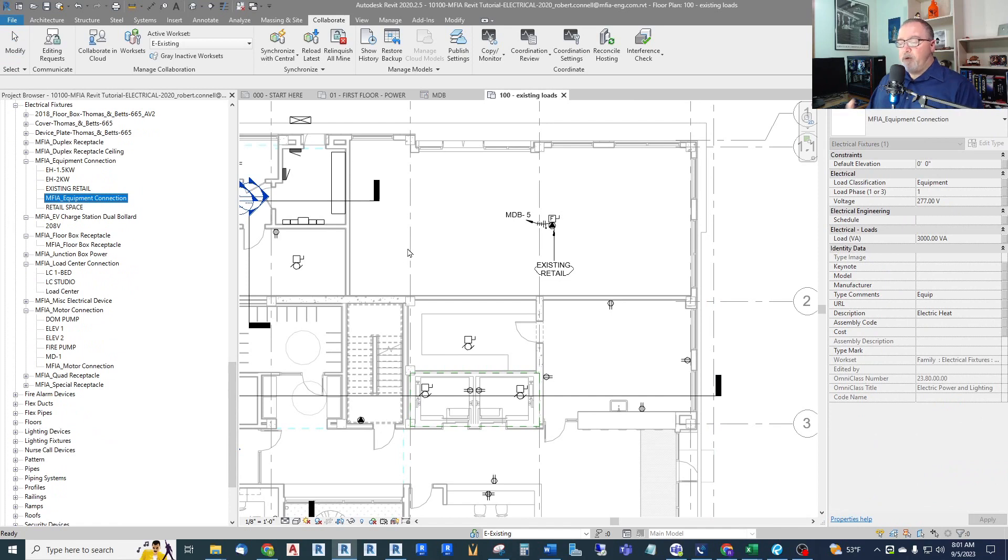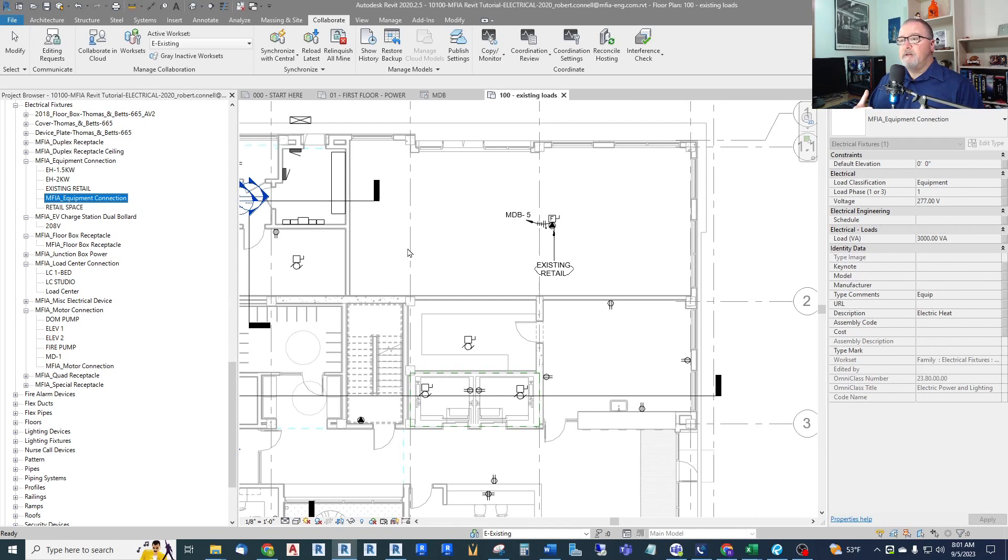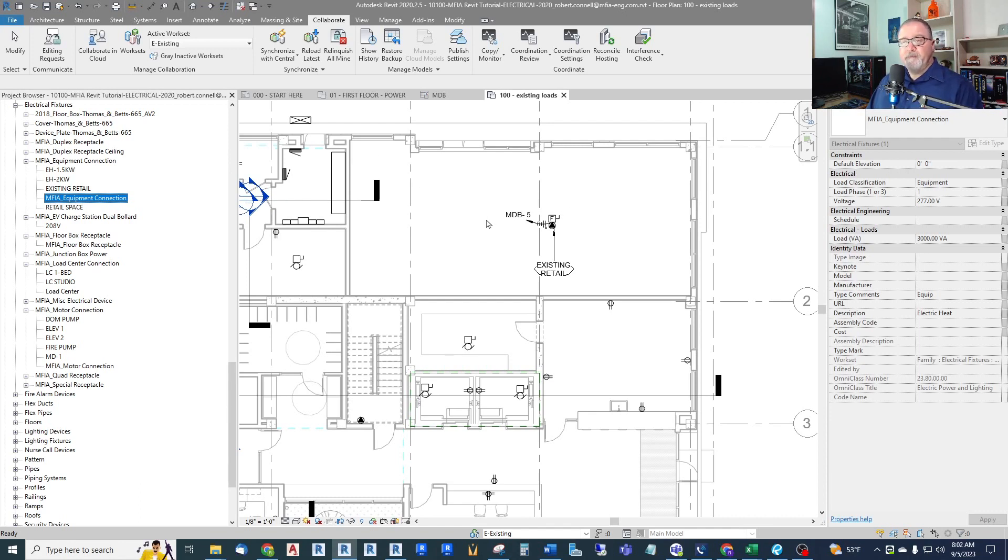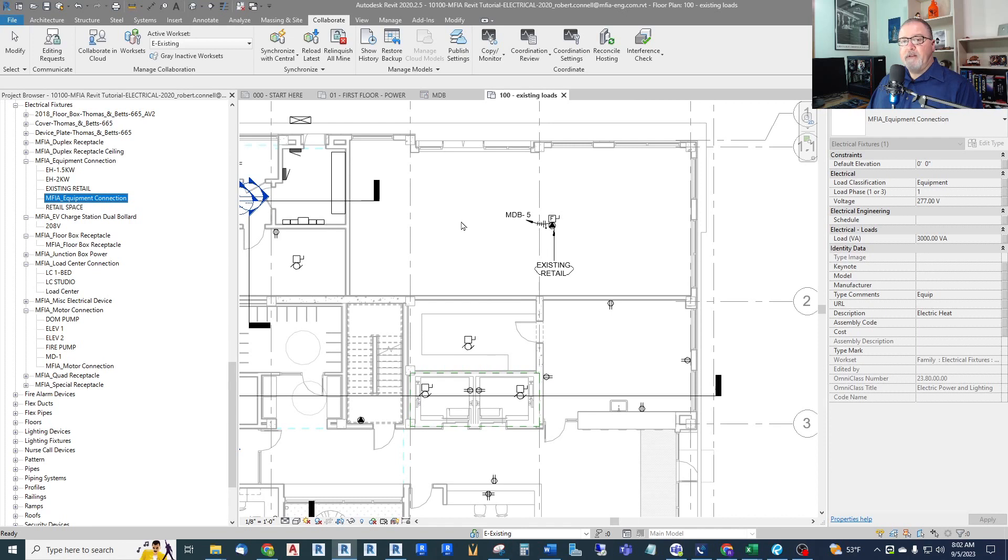But what I do is if I have an existing, I had a project where I had three panels of existing loads that I knew circuit by circuit what they were. I had good photos of the panels. I had good information about what's in the field. So I was able to do a more detailed approach. I did not know exactly where they were in the building. So what I decided to do was show the circuits in the panels, but not the receptacles in the view.